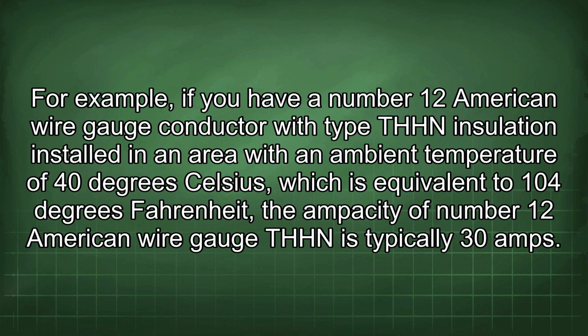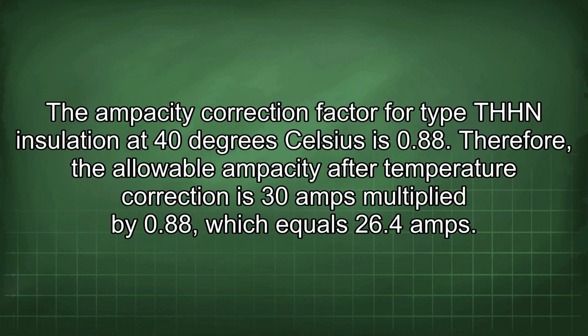For example, if you have a number 12 American wire gauge conductor with type THHN insulation installed in an area with an ambient temperature of 40 degrees Celsius, which is equivalent to 104 degrees Fahrenheit, the ampacity of number 12 American wire gauge THHN is typically 30 amps. The ampacity correction factor for type THHN insulation at 40 degrees Celsius is 0.88. Therefore, the allowable ampacity after temperature correction is 30 amps multiplied by 0.88, which equals 26.4 amps.